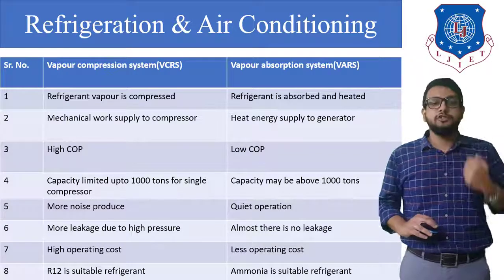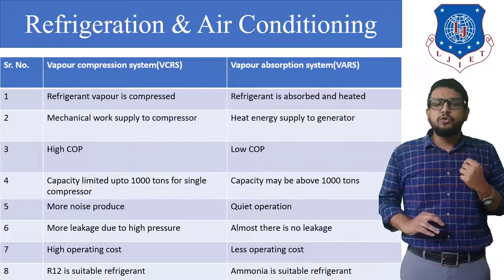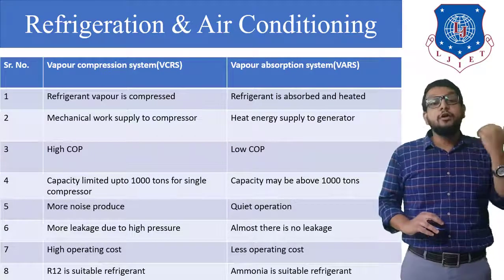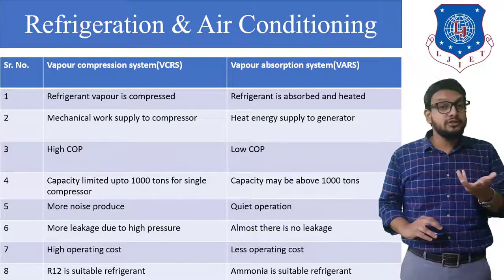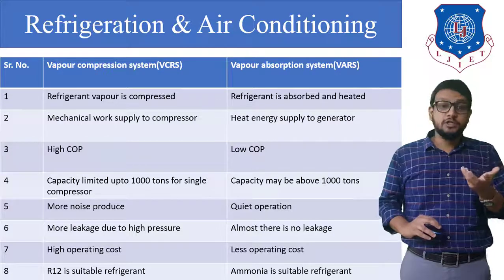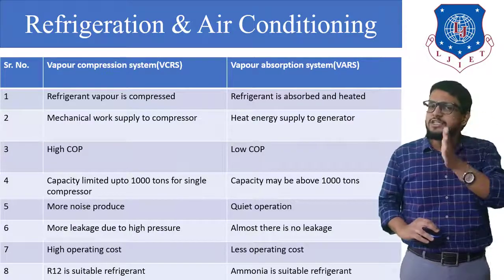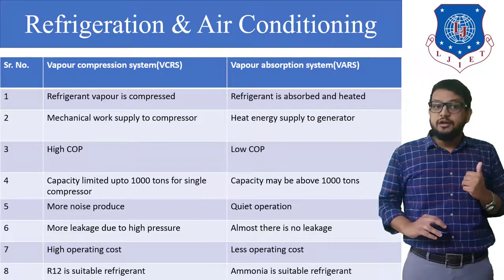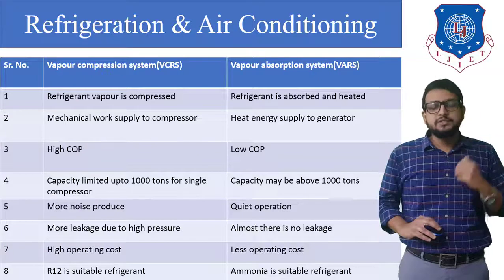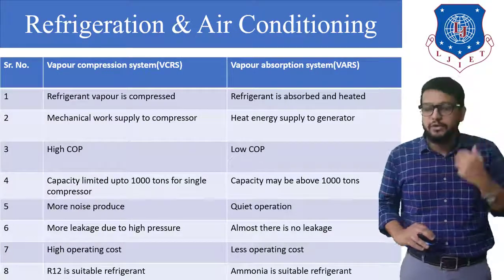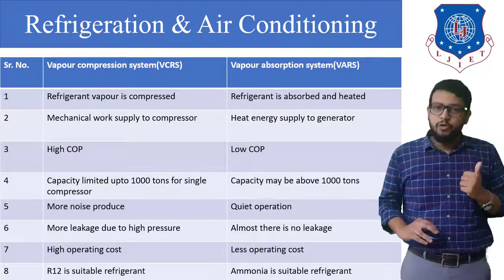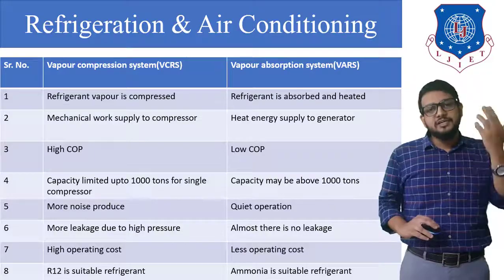Sixth, there is more leakage problem in the VCR system due to high pressure, whereas in the VAR system there is almost no leakage problem. Seventh, the VCR system has higher operating cost since electricity is consumed, whereas the VAR system only supplies heat energy to the generator so operating cost is much lower. Eighth, R12 is a suitable refrigerant for the VCR system, whereas ammonia is suitable for the VAR system because it can be easily absorbed in cold water. I hope you are clear with the VAR system and the differences. In the next session we will discuss the air conditioning system.